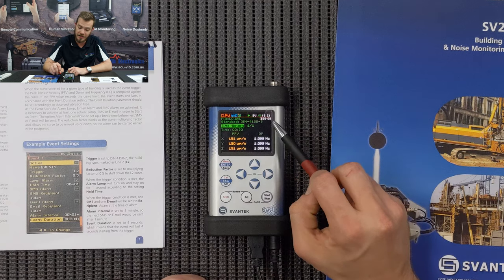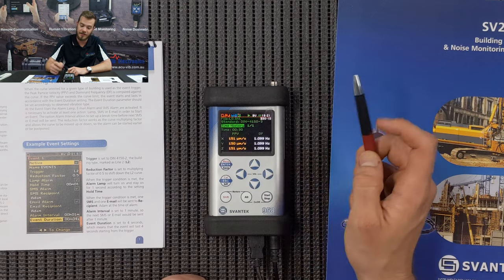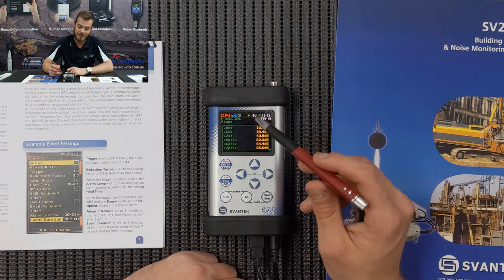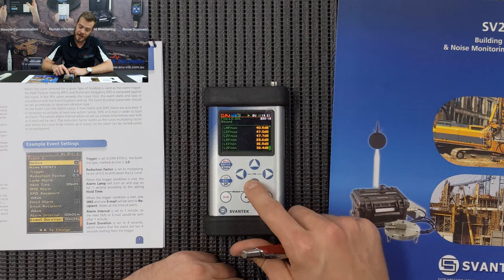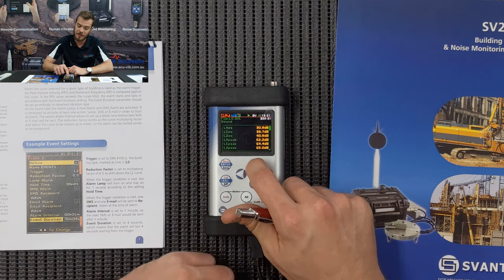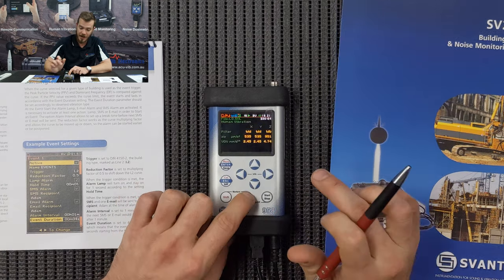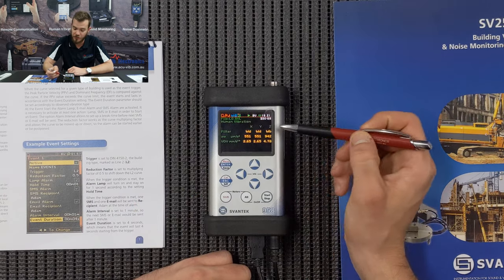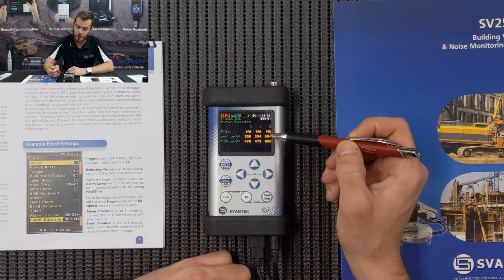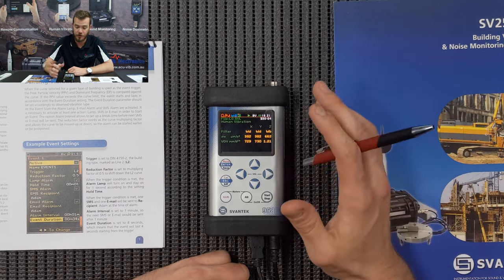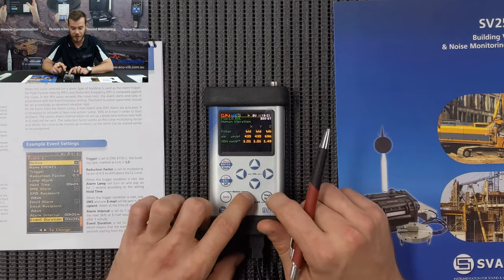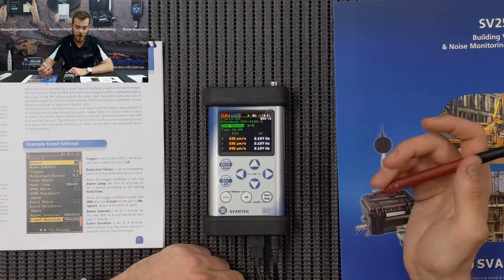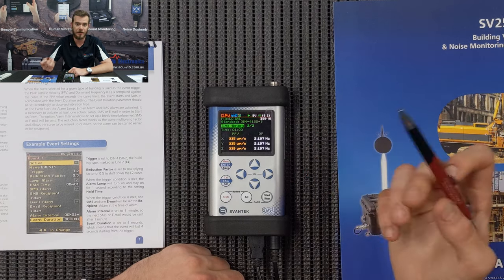And then what's going to happen is this is going to get to another 30 seconds and it's going to rotate into the next time history stamp. If we just press the alt and the down arrow, we'll have all of our sound profiles. So we can rotate down, see what's happening there, LEQ for the previous lot. If we press down again, we'll have a bit of further analysis. So some more instantaneous results on the weighted acceleration and also VDV results, which are pretty crucial for a lot of customers for human comfort. So let's scroll down and back at square one. And as you can see, we've got our 2 out of 2. History timeline rolling on, dominant frequency and PPV.